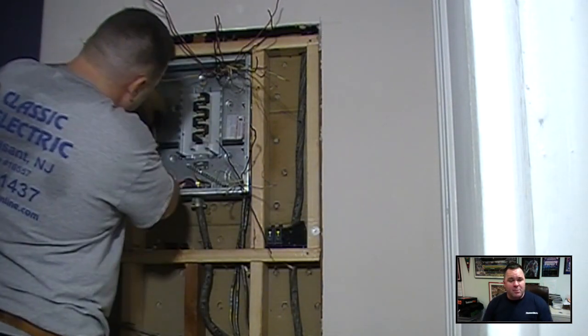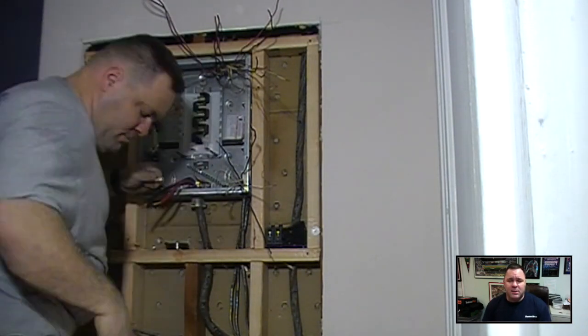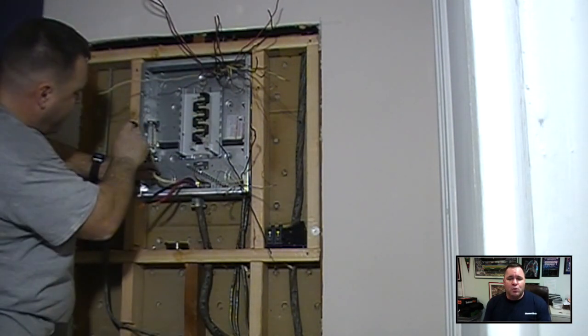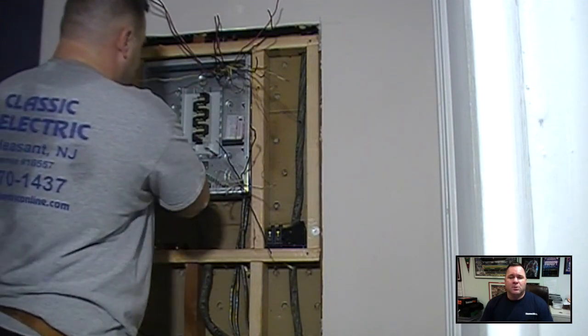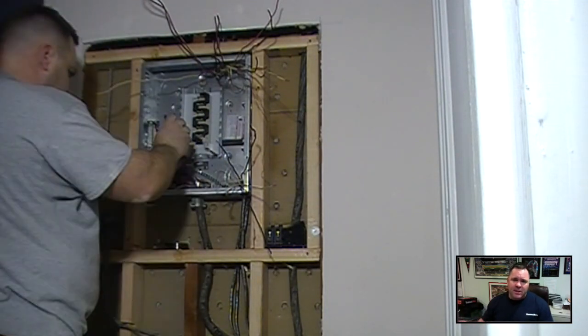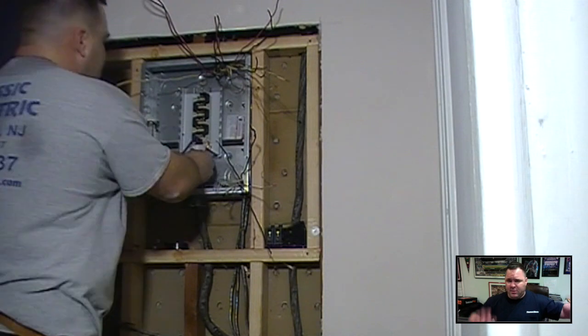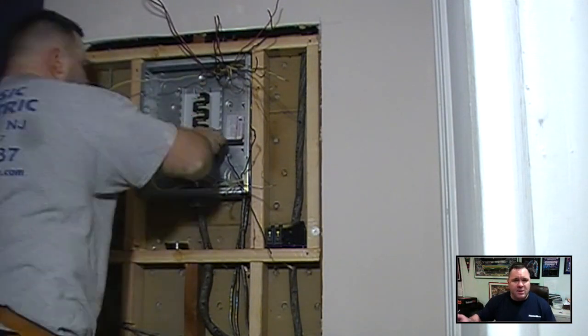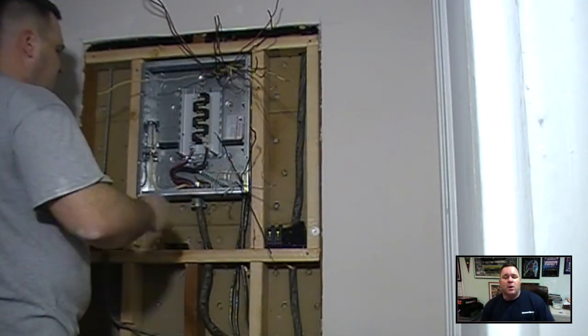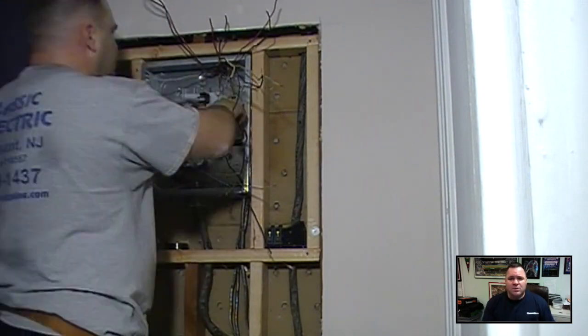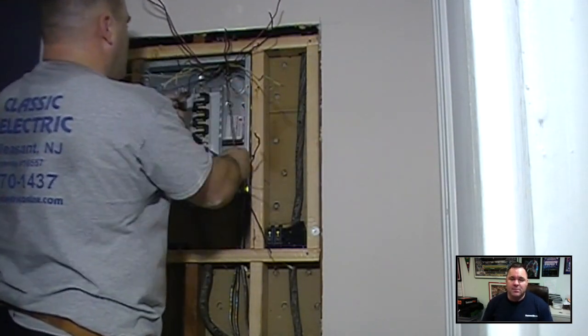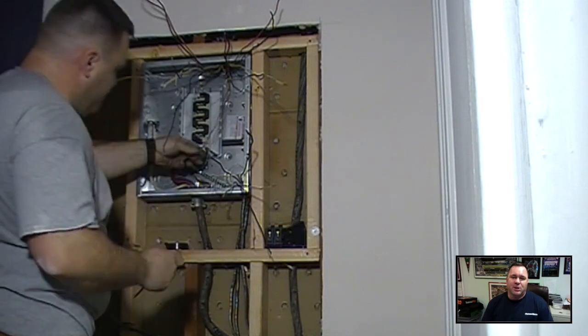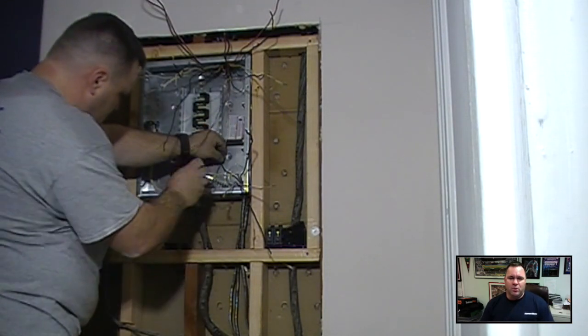This is a sub panel. The main disconnect is actually down in the basement, as it should be - they need to be grouped, and that's where they are. So there's a main breaker in the basement, and then a sub panel in each of the different apartments that have their mains down in the basement. When you do that, your neutrals and grounds need to be isolated, so you don't have what's known as objectionable current flow on your equipment grounding conductor.